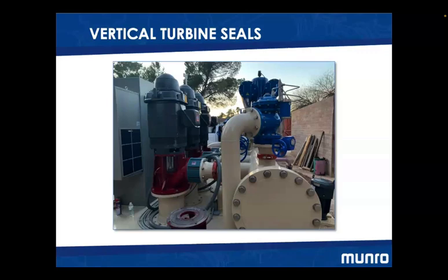Other applications might be where we're pumping water from a pond that has the opportunity to settle itself out. And when it settles itself out, we're not pulling near as much material into the pump that could cause damage to the seal. Thus, in turn, making the pump station look cleaner, last longer, and just be an overall better solution for the type of seal that we might use. So a couple of considerations is the style of water, the type of water we're going to be pumping, and overall cost can be a big difference too.